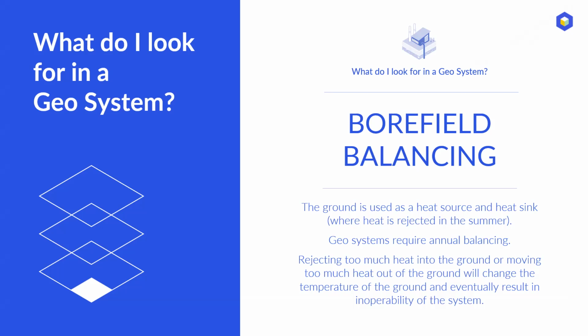So when we're designing and modeling geo-exchange systems, we model it first, but then when they're operational we're monitoring how many megawatt hours of heat we've pulled out of the rock in the wintertime, and how many megawatt hours of heat we're pulling out of your building and putting back into the rock in the summer. We want these things to be relatively the same so we can try to keep your bore field balanced, essentially.